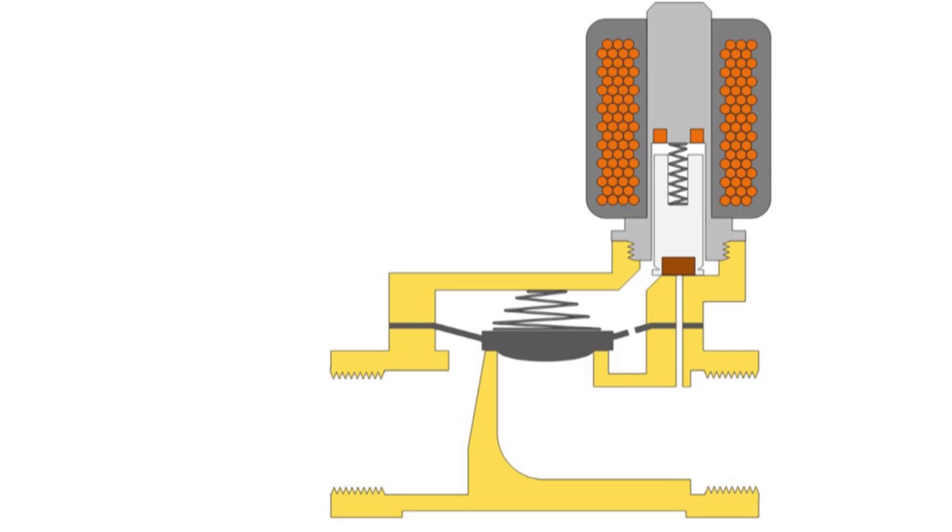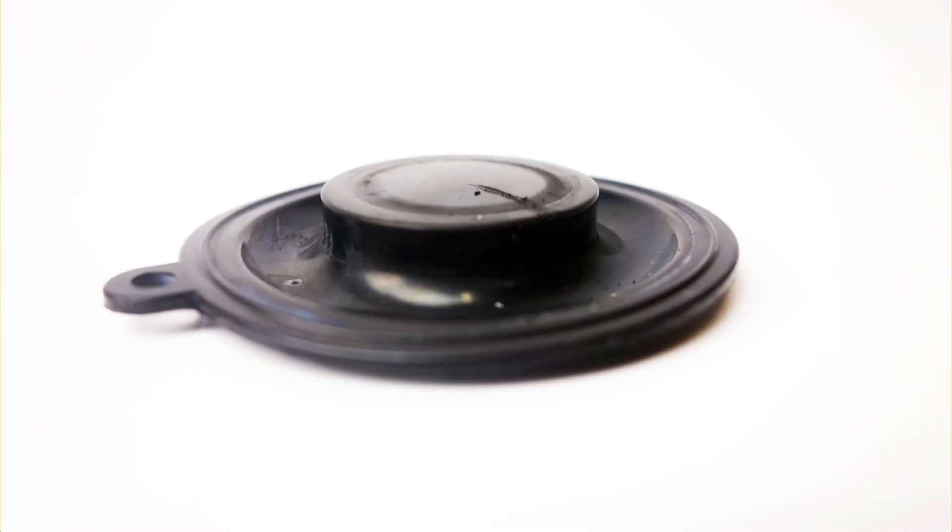If the valve doesn't shut off or leaks, inspect and replace damaged or worn membranes, seals, and o-rings. Even a very small leakage can cause the valve to malfunction.